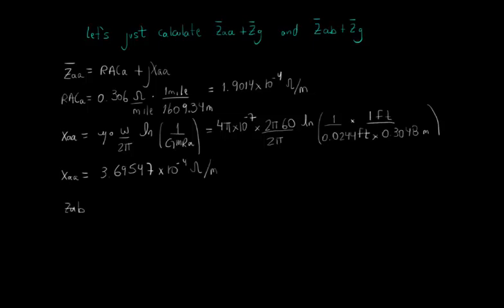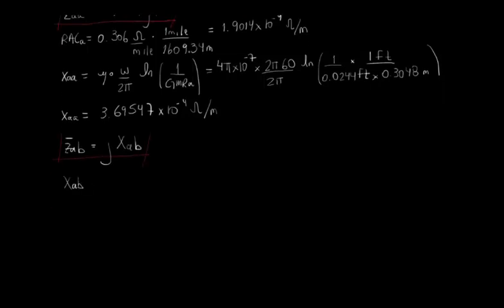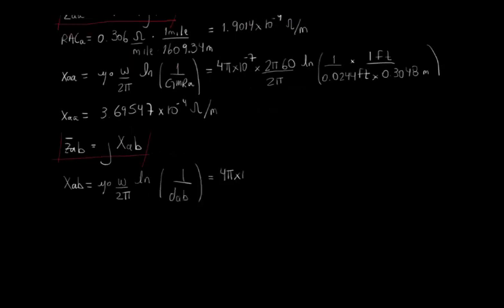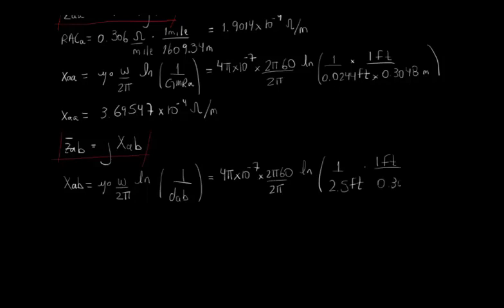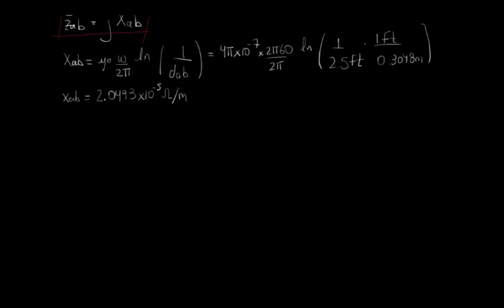Applying the expression for XAA, we get that it is equal to 3.69547 times 10 to the power of minus 4 ohms per meter. We know that ZAB is equal to j times XAB. Applying the expression from the manual, again paying attention to convert the distance units to meters in order to check the results with OpenDSS, we find that XAB is equal to 2.0493 times 10 to the power of minus 5 ohms per meter.